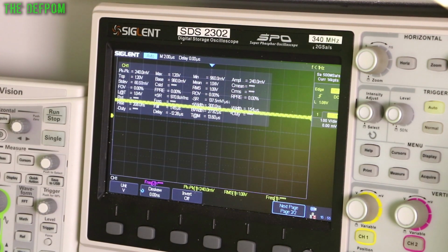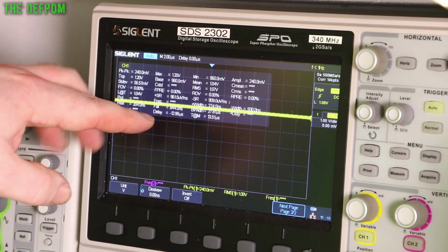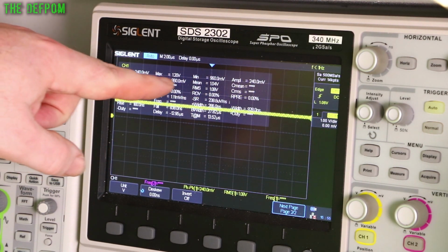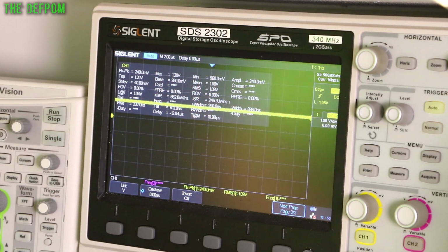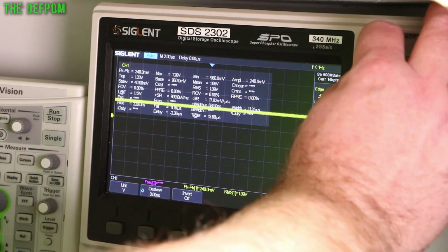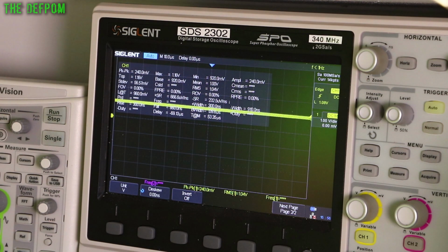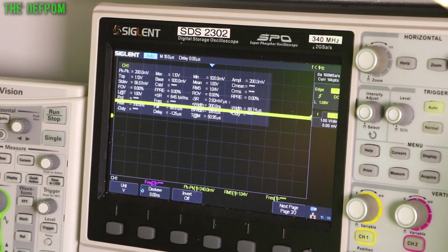Fluctuating very slightly. Now there's a lot of high frequency noise in here, which makes it a little bit trickier to actually get the reading, because you can see you've got a minimum and maximum here which are outside of that range. Obviously, it's doing a bit of averaging there because it's got high frequency noise. There's a lot of ripple in that particular section because this is the way that power works. Anyway, so I've got that 1.05 volts plus or minus 0.03. So as long as I'm hovering around that 1.05, then that should be good.